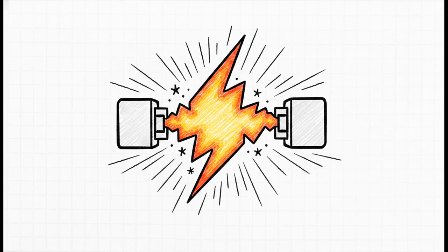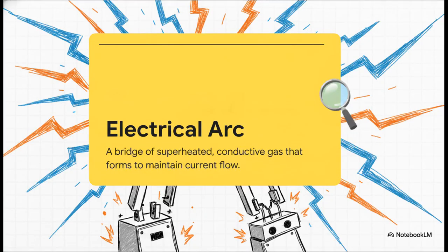Now, you might think that simply opening a breaker instantly stops the electricity, right? But here's the thing. Mechanical separation does not equal electrical interruption. The instant those contacts pull apart under a heavy load, the electricity actively fights back. It wants to keep that current flowing. And how exactly does it fight back? Well, it forms an electrical arc.